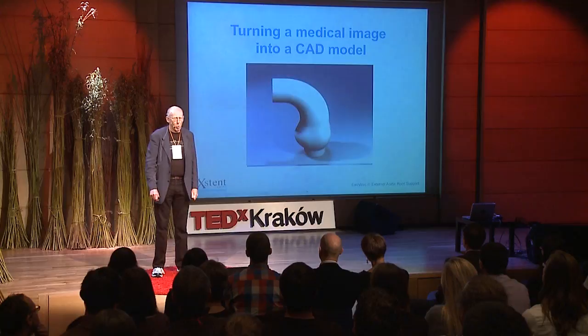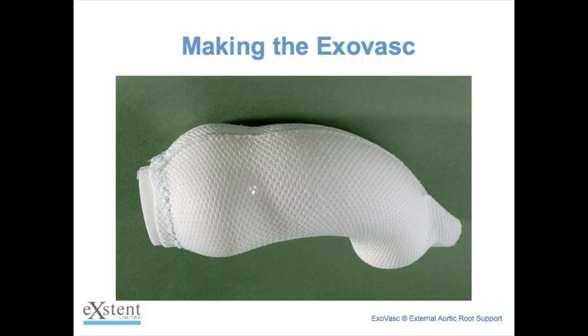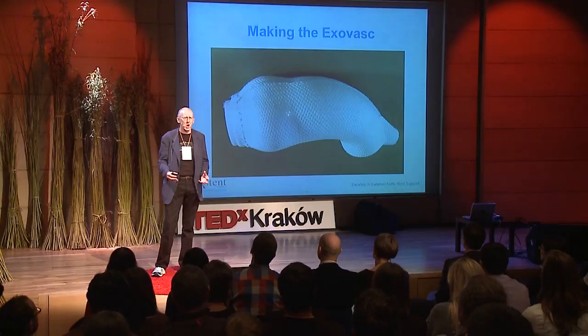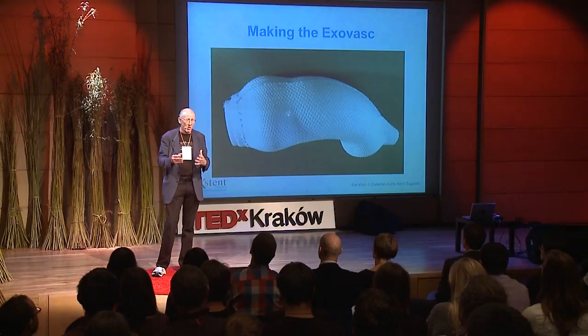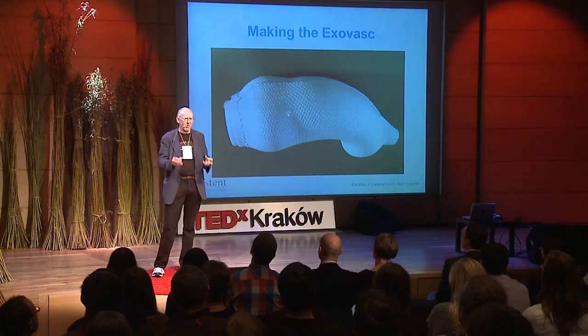We started by organizing image acquisition from MRI and CT imaging machines, from which to make a model of the patient's aorta. This is a model of my aorta — I've got a real one in my pocket if anyone would like to look at it. You can see it's quite a complex structure: it has a funny trilobal shape at the bottom which contains the aortic valve, then comes back into a round form and tapers and curves off. We went through an iterative process of producing better and better CAD models, then turned each model into a solid plastic model using rapid prototyping. We then used that former to manufacture a perfectly bespoke porous textile mesh which perfectly fits the aorta — absolutely personalized medicine. Once you've made it, the installation is quite easy. Professor John Pepper, cardiac surgeon, put the first one in, didn't like it, took it out, put the second one in — four and a half hours on the table and everything was done.